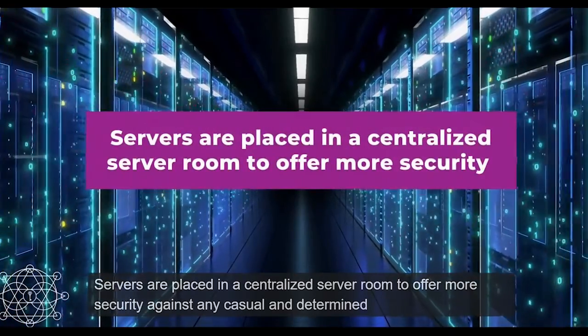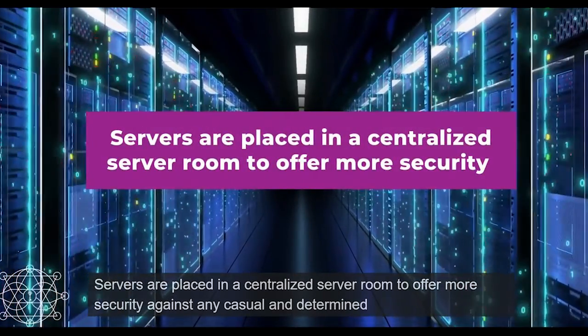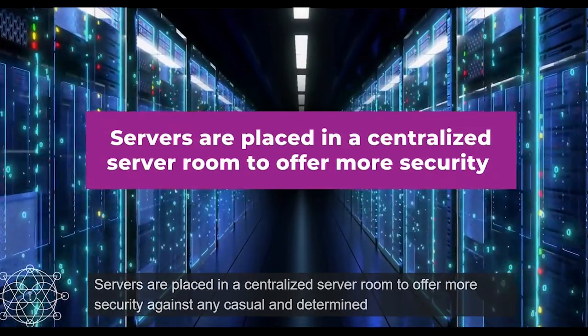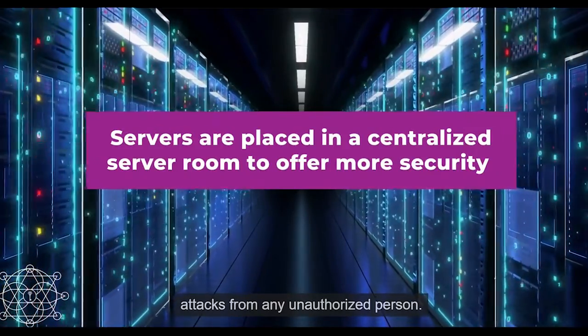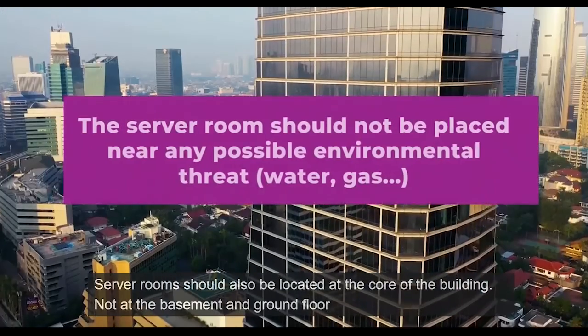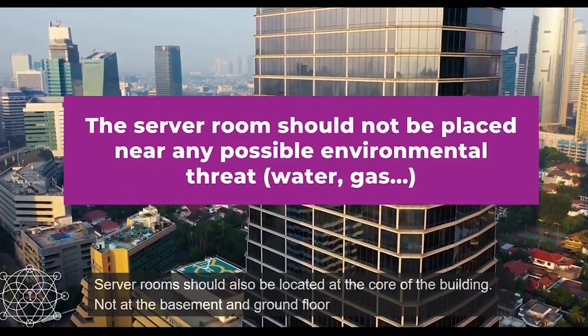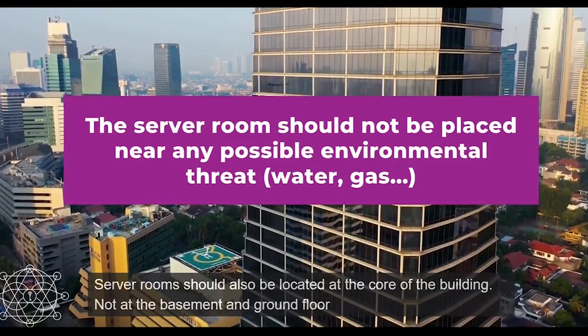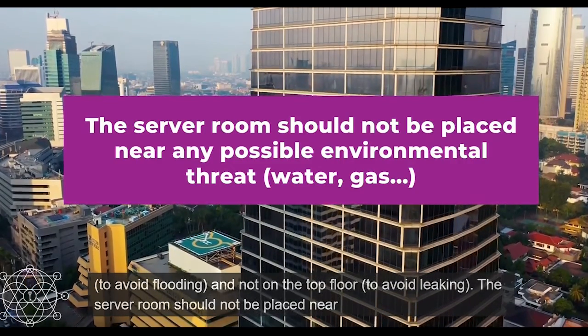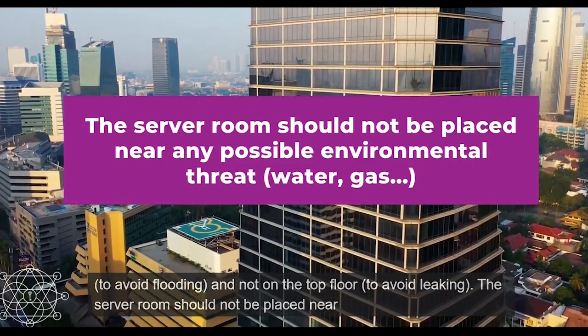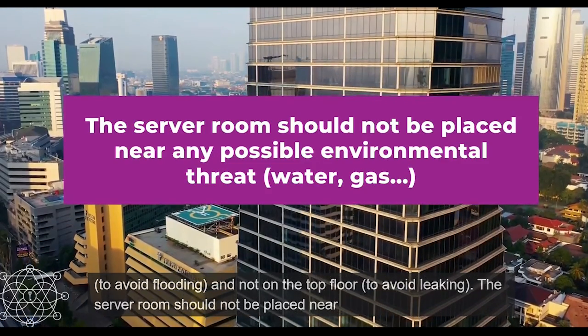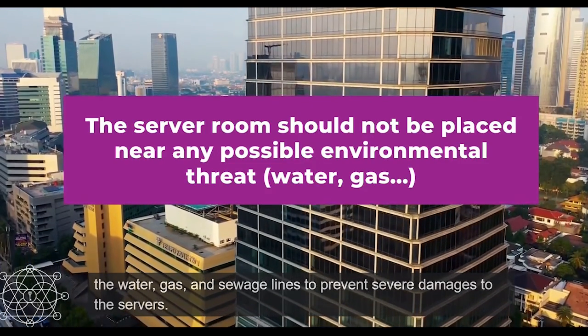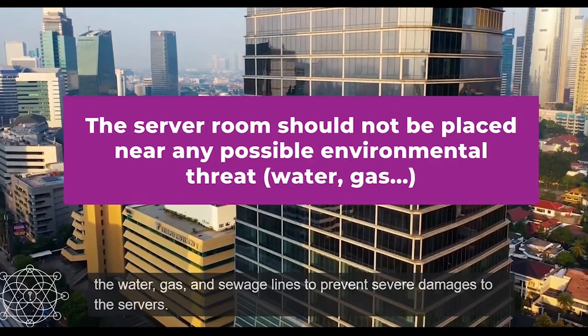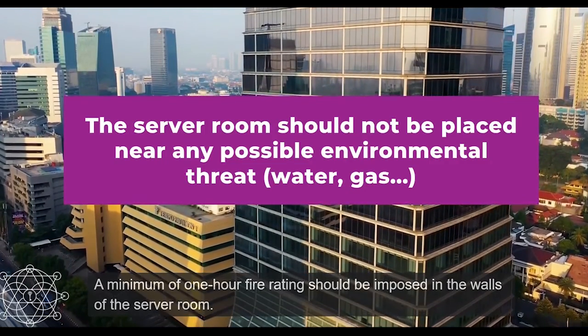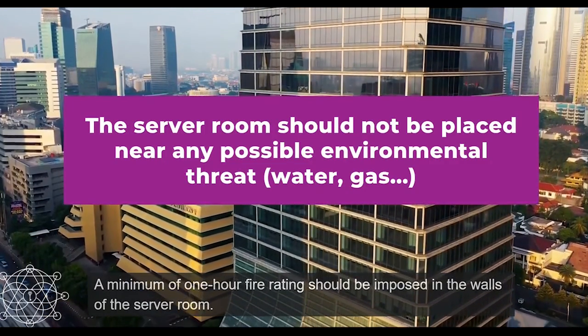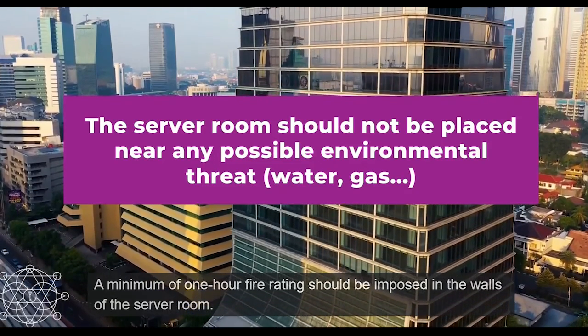Servers are placed in a centralized server room to offer more security against any casual and determined attacks from any unauthorized person. Server rooms should also be located at the core of the building, not at the basement and ground floor, to avoid flooding, and not on the top floor to avoid leaking. The server room should not be placed near the water, gas, and sewage lines to prevent severe damages to the servers. A minimum of 1 hour fire rating should be imposed in the walls of the server room.